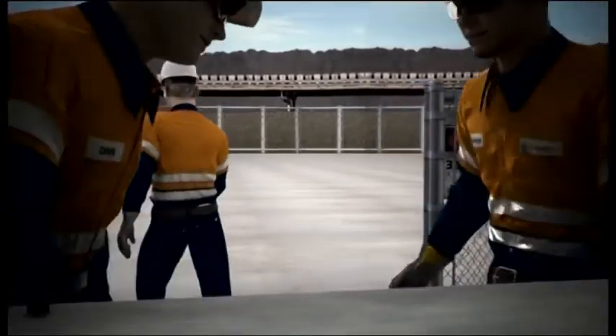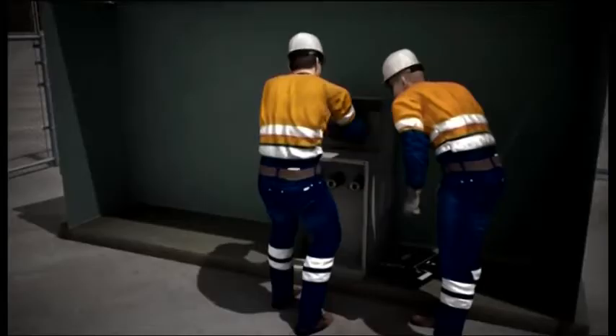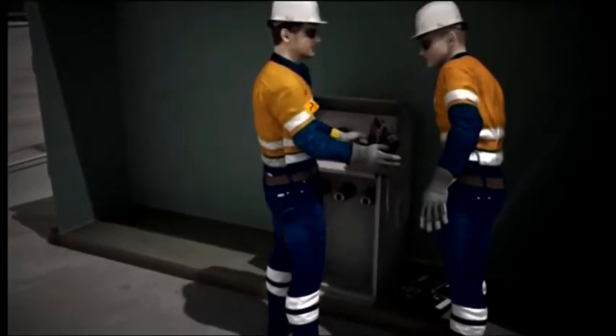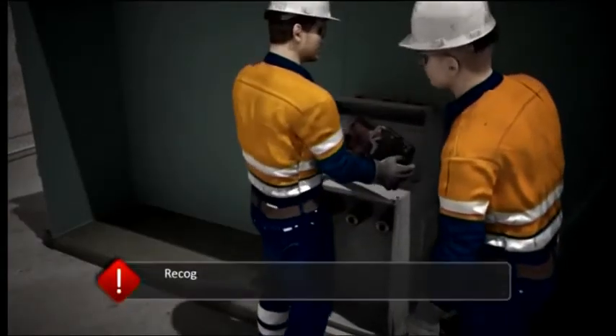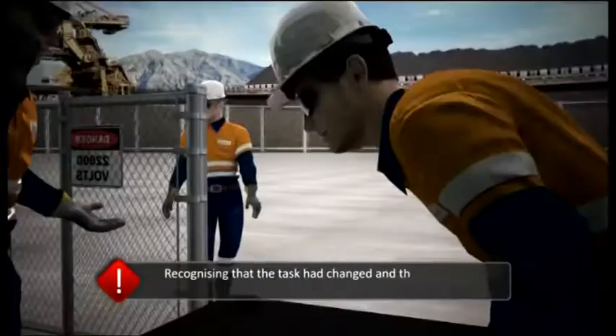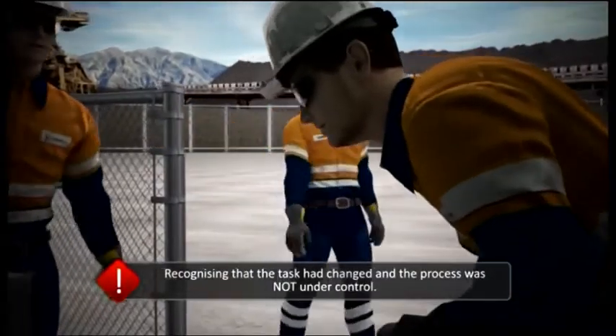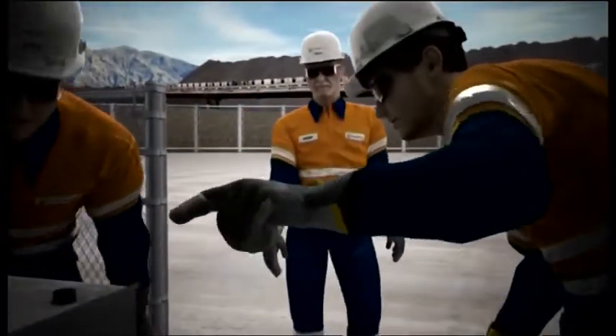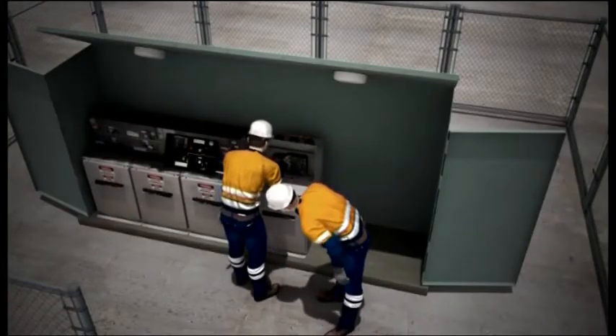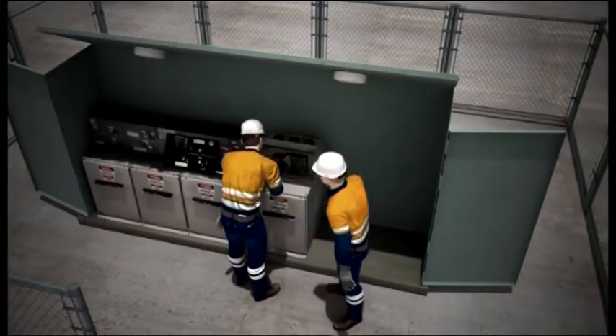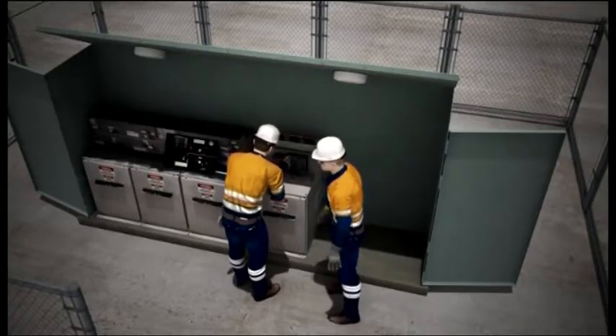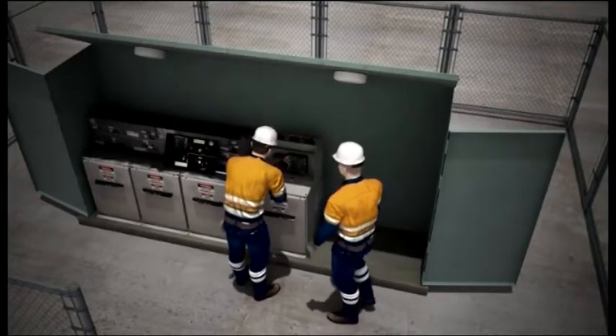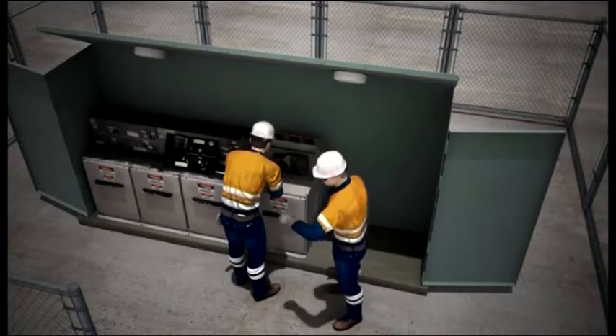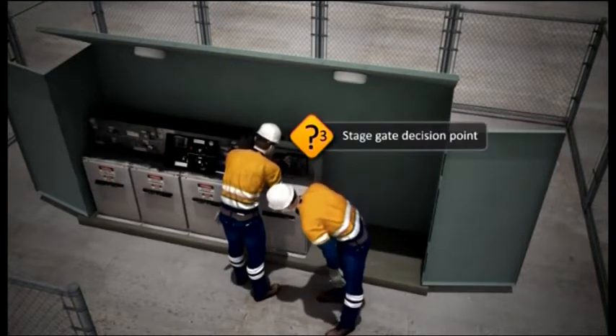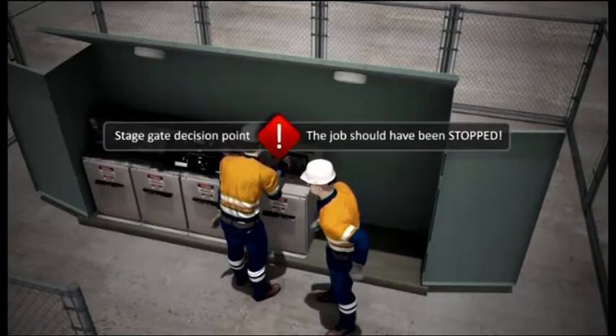This became more evident when the springs on the second mechanism fell apart on removal. This was the second decision point where the job should have been stopped, recognizing that the task had changed and the process was not under control. To keep the springs compressed on the third mechanism, Dave used a makeshift drill, tap and screw technique to make up for his lack of knowledge of how the high voltage isolation mechanisms worked. Yet another decision point where the job should have been stopped.